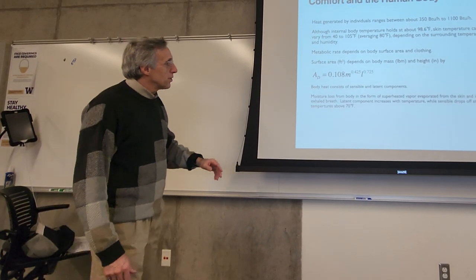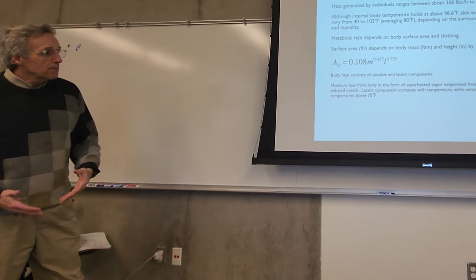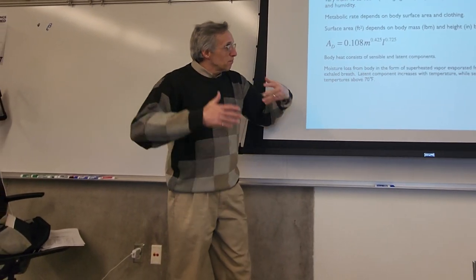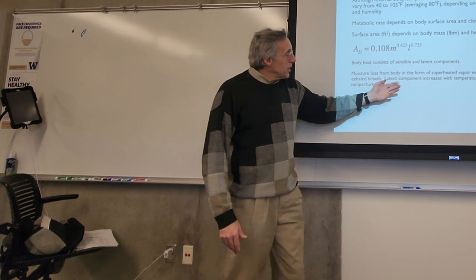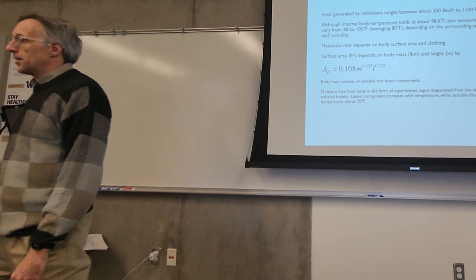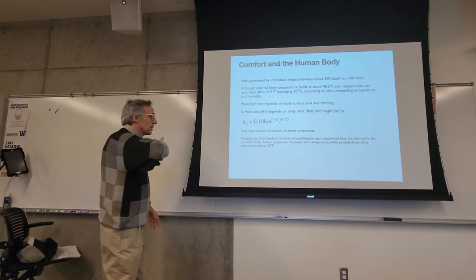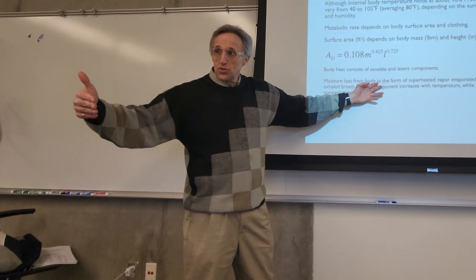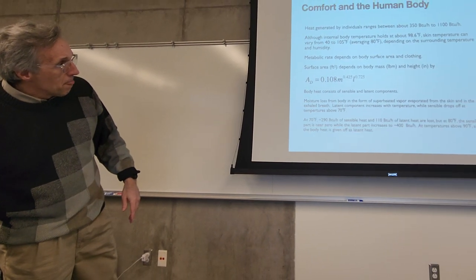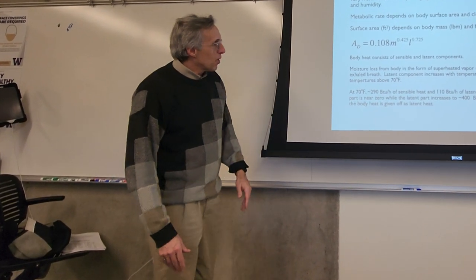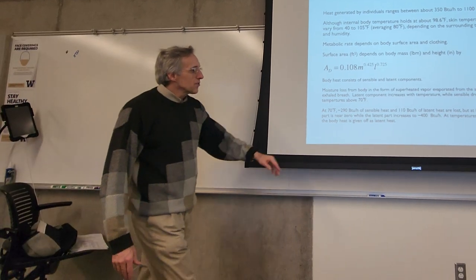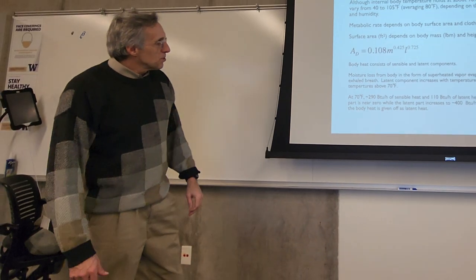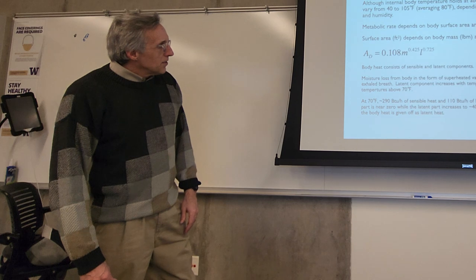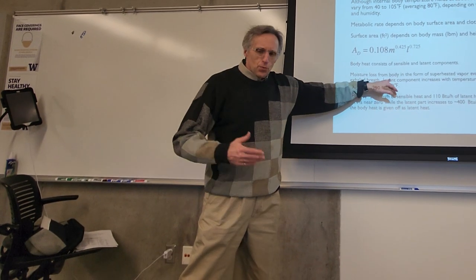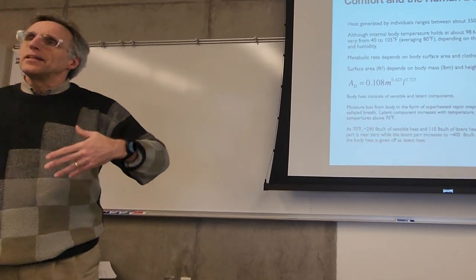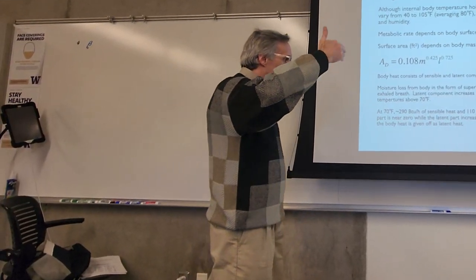And we can divide that into sensible and latent components. Interestingly, when we're at rest, most of our heat transfer is coming as sensible heat. As we increase our activity, the sensible part starts to drop off, and we get more latent energy. At 70 degrees, about 290 BTU per hour sensible and 110 of latent heat are lost. But at 80 degrees Fahrenheit, the sensible part is near zero. I said that wrong. I mean as the temperature of the environment that we're working in goes up, our sensible component goes down and our latent goes up.